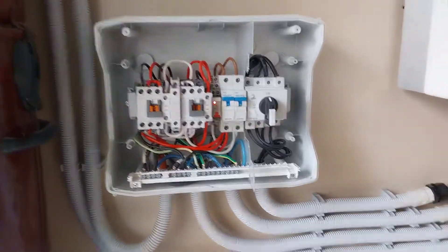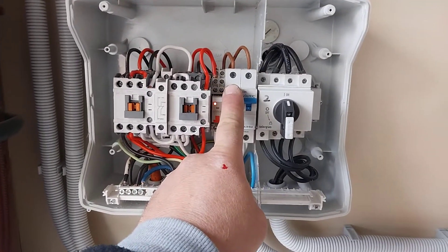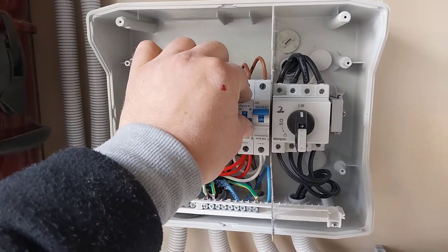Let's start by turning off the grid. As you can see, the backup contactor stays in because this has got power on it — everything's fine here. Now let's turn that grid back on and see what happens if something goes wrong: batteries dead flat, PV array problem, inverter breaking, whatever.